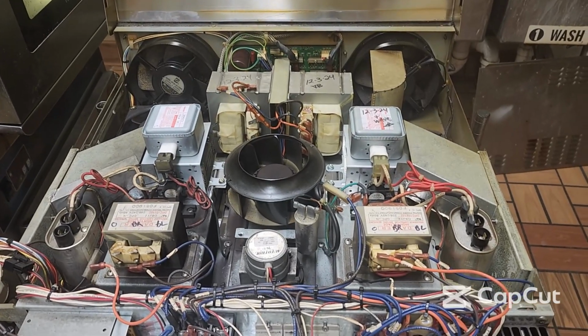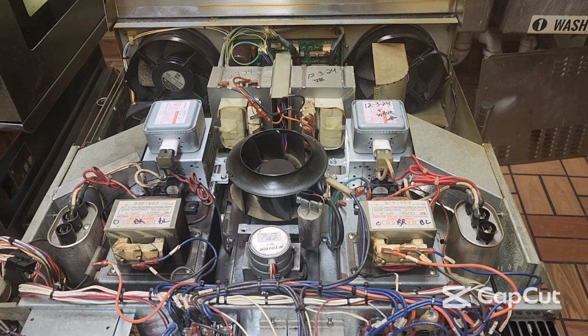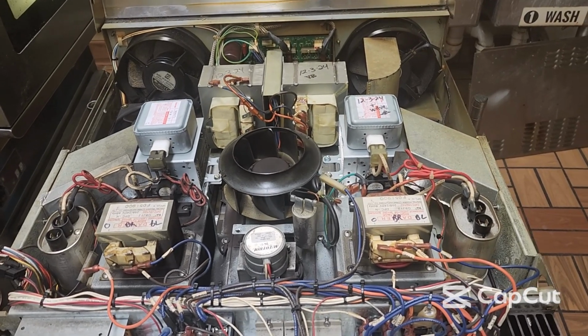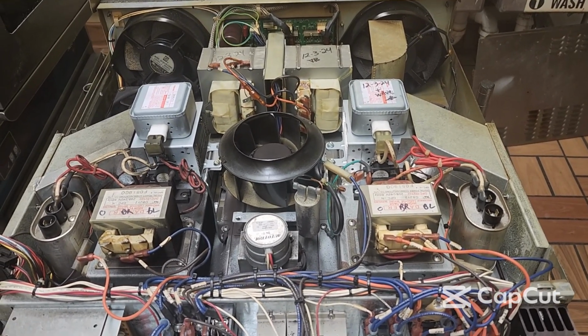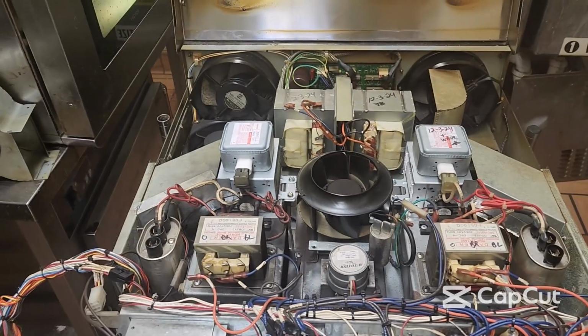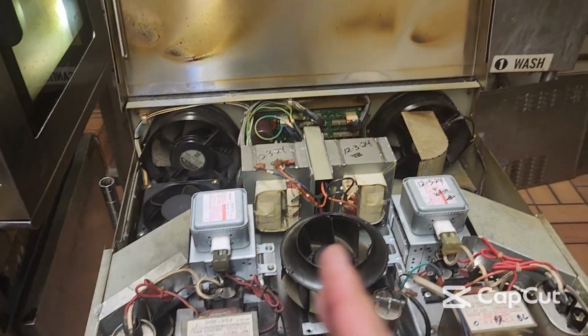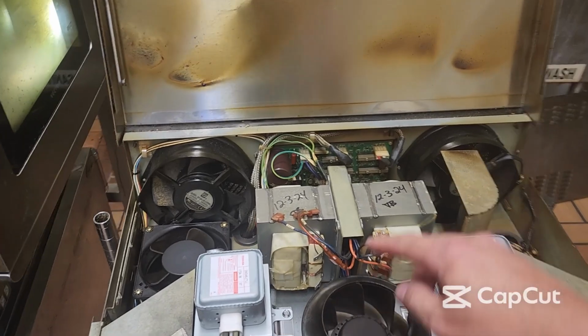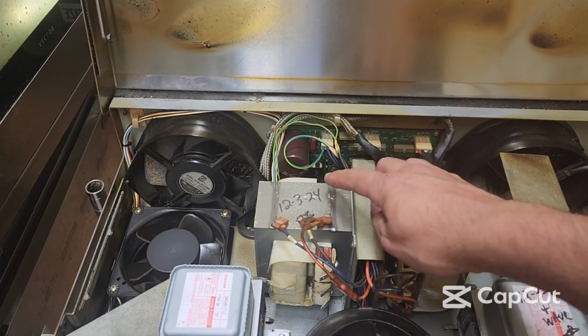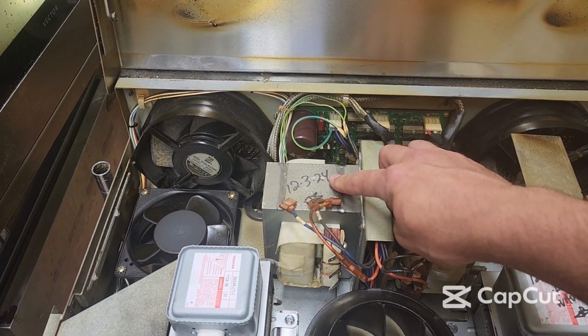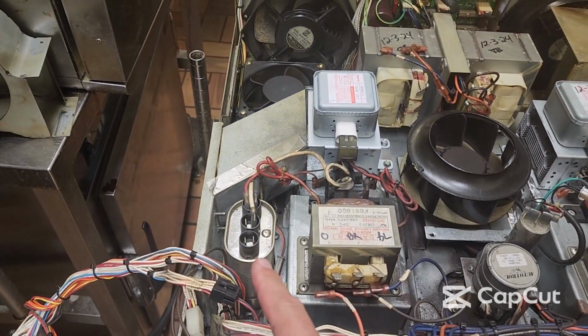Now, if it was high amps, there's a few things that cause that versus low amps. High amps, being over 20, is usually related to two specific things: your high voltage transformer or your high voltage capacitor.